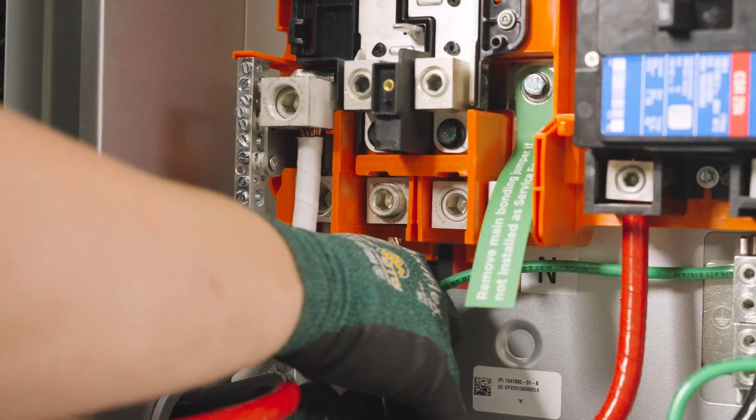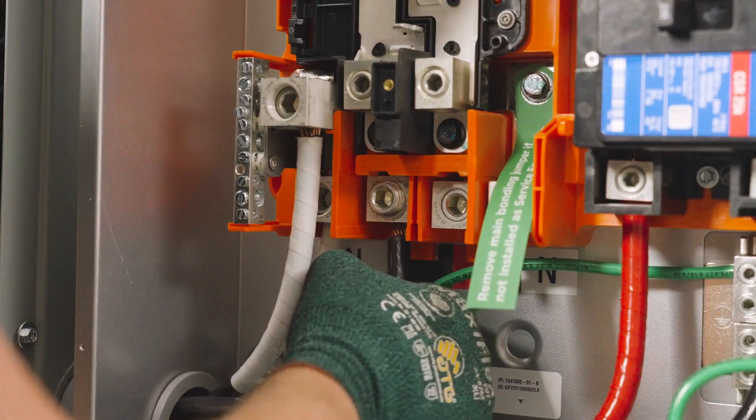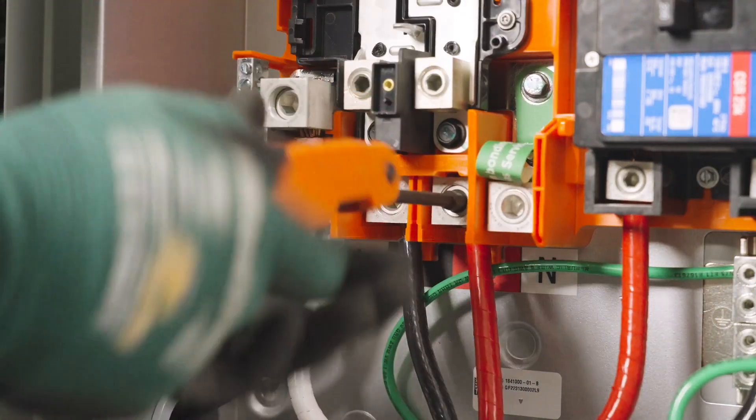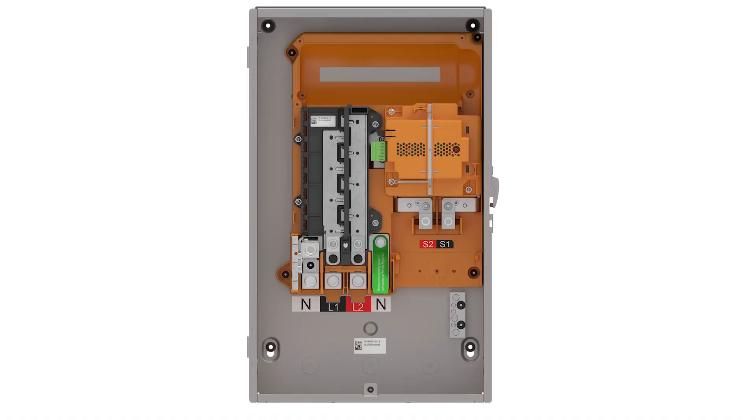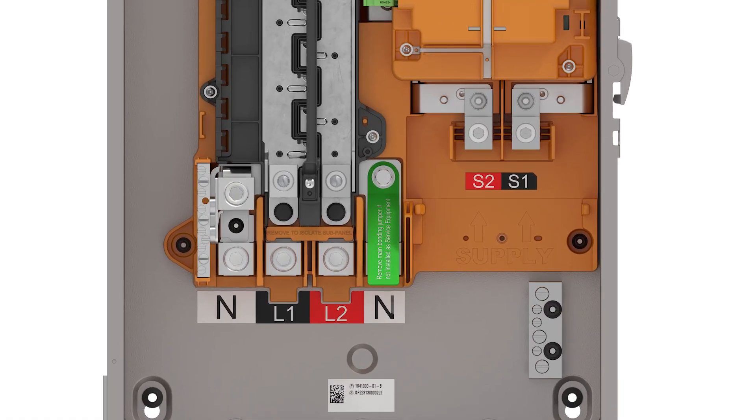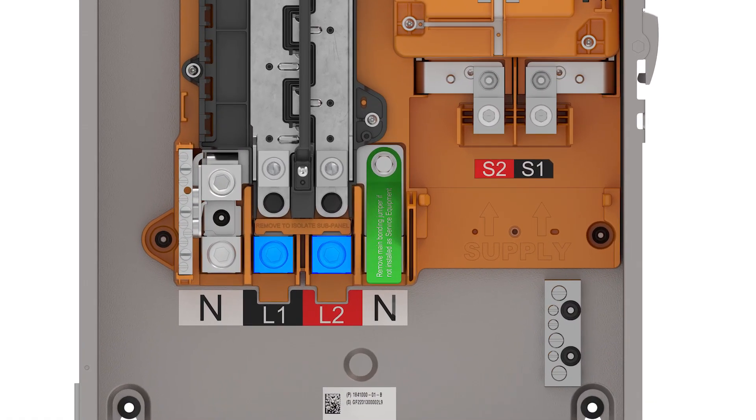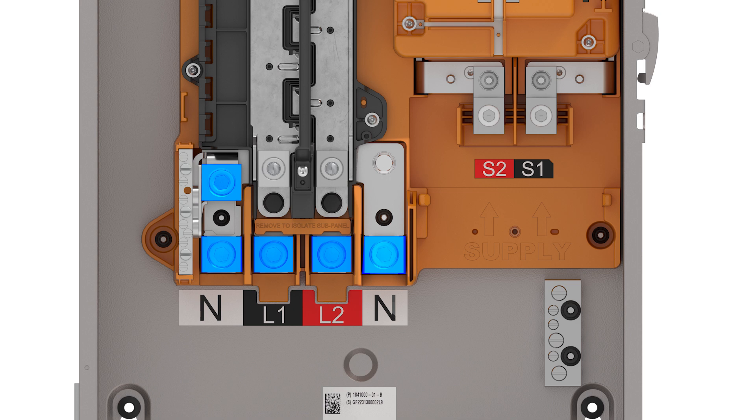The next step is to connect the outgoing conductors that feed the backup load center. Line 1 and line 2 conductors are terminated on these lugs. Neutral and grounding conductors are terminated on their respective lugs. These five lugs are rated to accept two wires each provided that they are the same size and material.